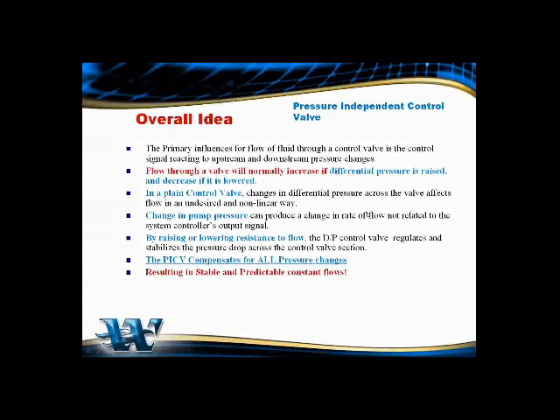And with a plain control valve, the differential pressure across the valve affects flow in an undesired and nonlinear way. So you will not get your optimized control if you're just using a plain control valve. Changes in pump pressures can produce changes in flow rates, and they may not even be related to the system controller's output signal. So if you can control this and actually compensate for the pressure changes, you will have results of much more predictable and stable flows.